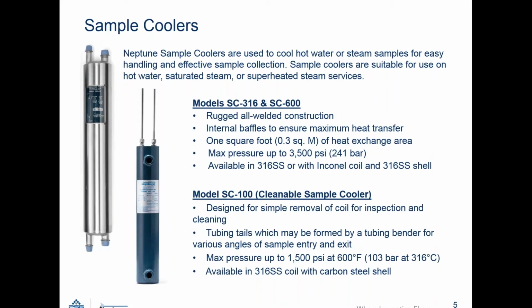Sample coolers. Sample coolers are generally used in boiler applications where, when the boiler is being treated, the water needs to be tested. We have what we call sample coolers that can take in a sample from the boiler and cool that sample down. We have 3 different versions, which is the SC316 and the SC600, which is an all welded construction, meaning you can't take it apart. We have baffles. They each have baffles. It transfers the heat to cool down the sample properly.